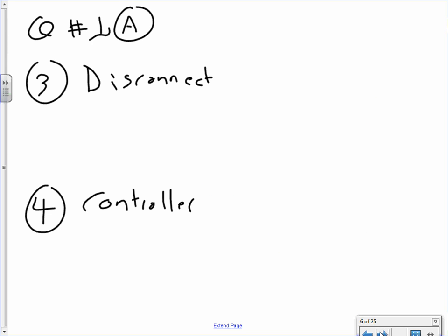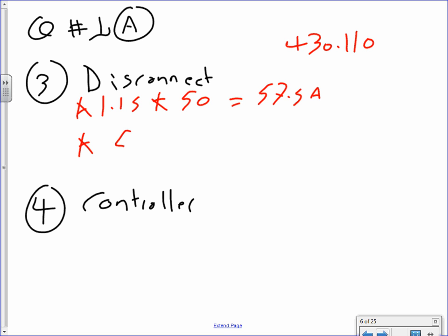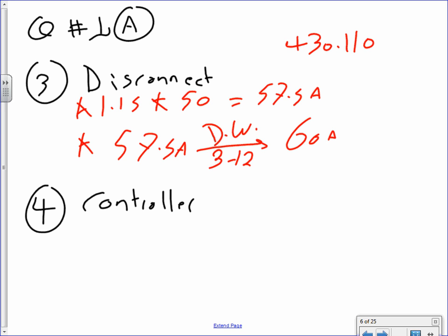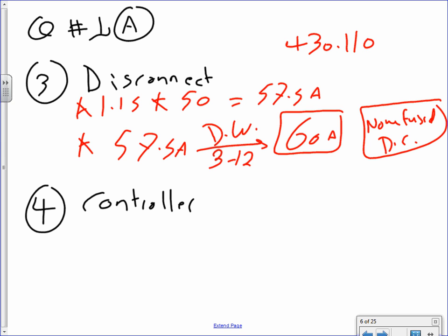Okay, let's go to the disconnect. Next, number 3 is the disconnect. For disconnects, if you remember yesterday, you go to 430.110. It's very simple. It takes the 1.15, multiplied by 50, and that will get you 57.5 amps. From there, you take the 57.5 amps to Table 3-12, and that'll get you a 60 amp non-fused disconnect. There's no fuse in it, exactly like the one you're looking at here. Any comments, any questions? Again, we did an example yesterday. I thought I'd emphasize it with another example today.